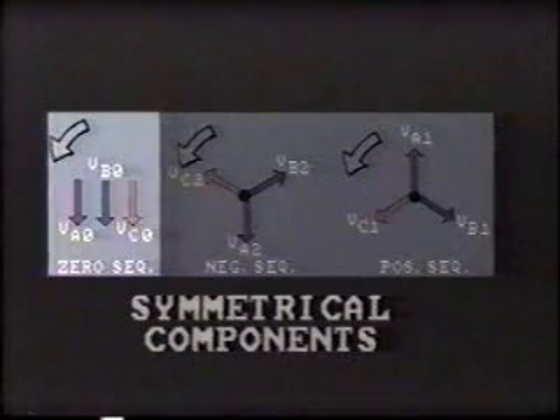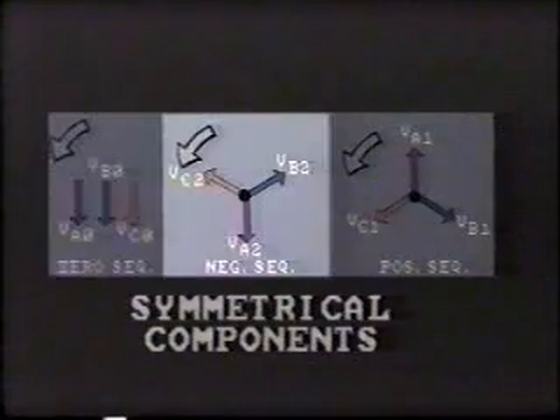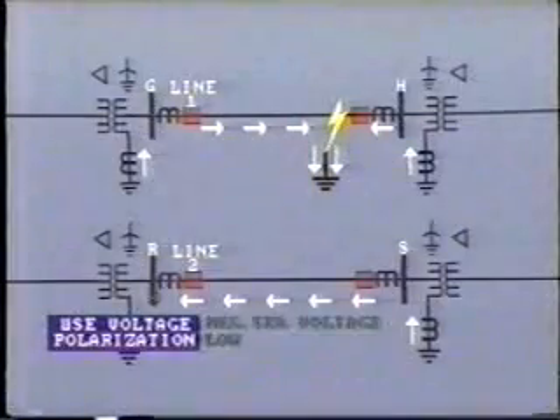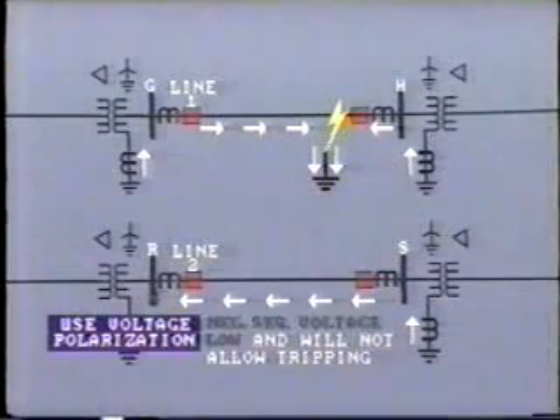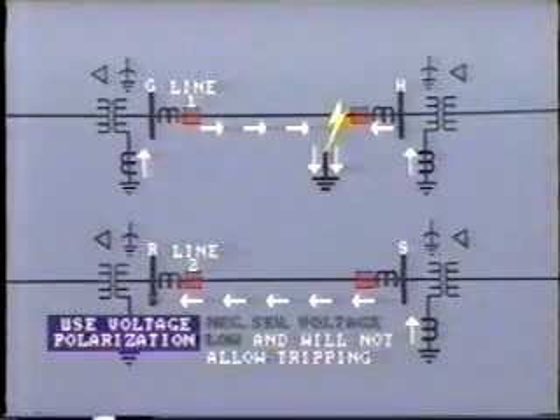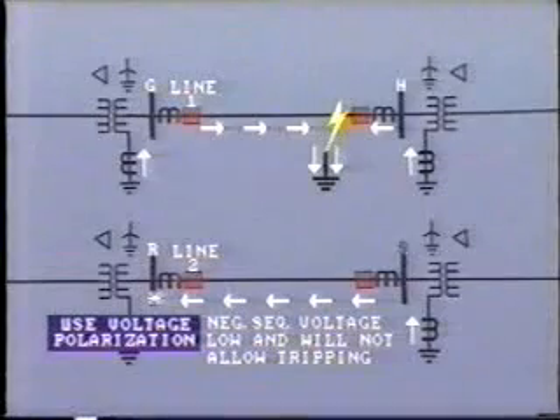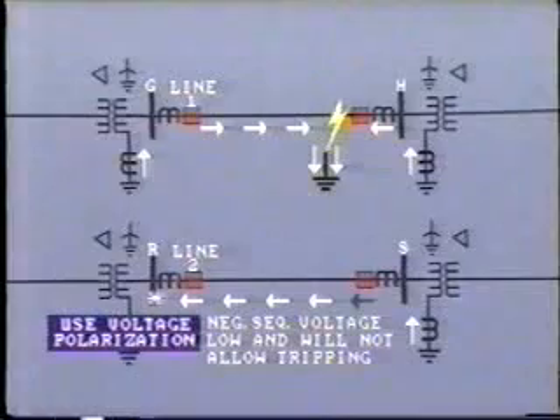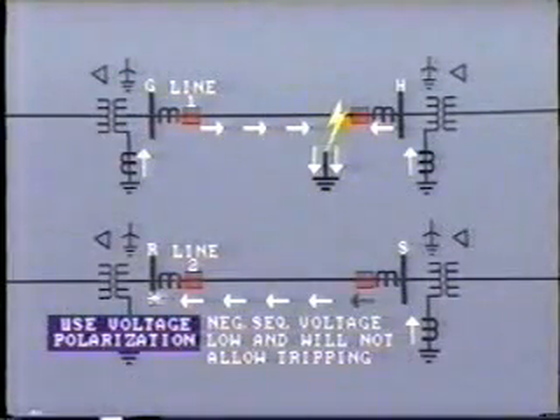Remember, zero-sequence components are all in phase, while the negative phase components are equidistantly spread across the three phases. So the magnitude of induced negative sequence voltage is extremely low, and therefore should not interfere with voltage polarization using negative sequence components measured on line 2. Of course, application of negative sequence polarization would not prevent opening of the breaker at bus S, because here the current is actually entering the line, that is, in the tripping direction.